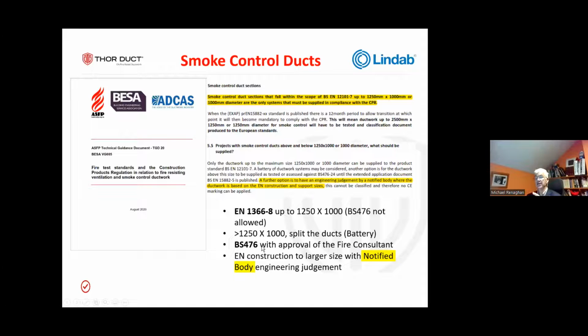Now, BS 476 is a lower performing duct. It is not tested in any way like EN 1366, it just isn't. And then finally, the fourth one is you can construct the larger ducts to the EN construction with the approval of a notified body giving an engineering judgment. And I can tell you now, you're never going to get one because they ain't going to do it. So that's the reality with smoke ducts.